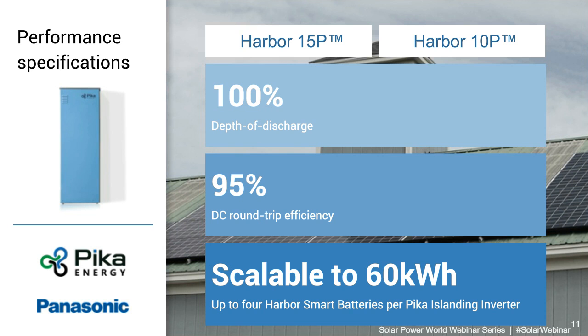But you have an assortment you can choose from. You could do 30 kilowatt hours and have 10 kilowatts of PV, but the point being you can scale this pretty generously compared to other systems, and you don't need additional supervisory controls or switch gears in order to do that. They all just click together on that same DC breaker.